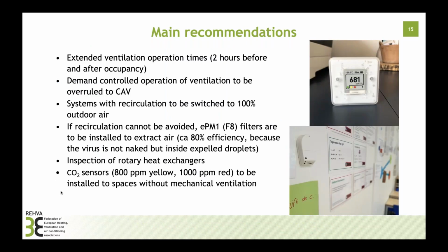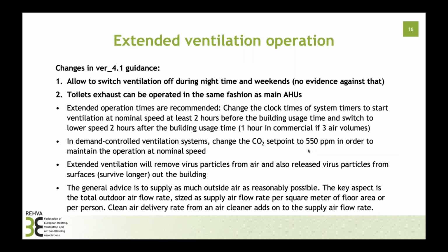So in the Nordic climate I am representing, the main recommendations which we have seen most important are for the ventilation operation time, that it should be extended when demand controlled ventilation is overruled, and systems with recirculation, if used in some countries, should be switched over to 100% outdoor air. And if that would not be possible, then improve return air filtering efficiency, and also inspection of rotary heat exchangers, which are the most common heat recovery equipment in public buildings in many countries. And then I will come back later to these CO2 sensors, which mainly apply for the buildings which do not have mechanical ventilation systems.